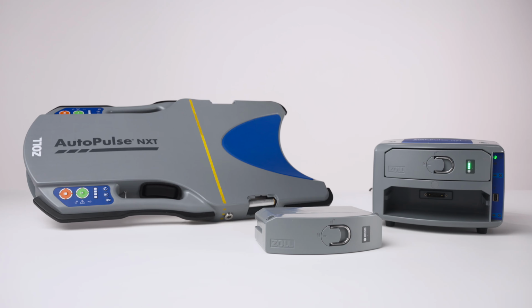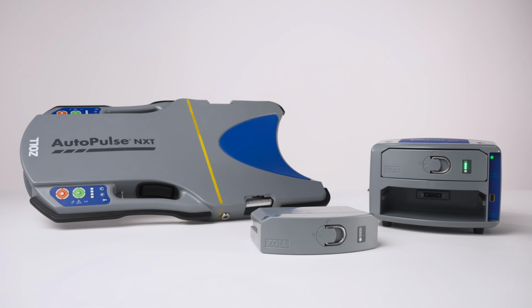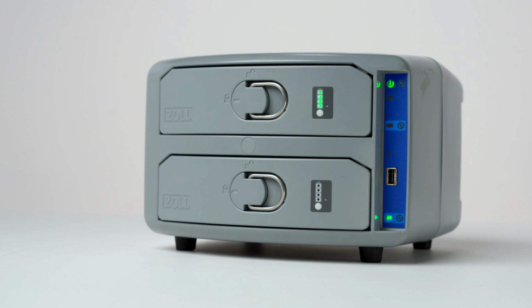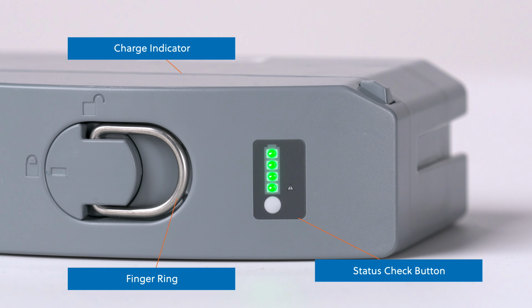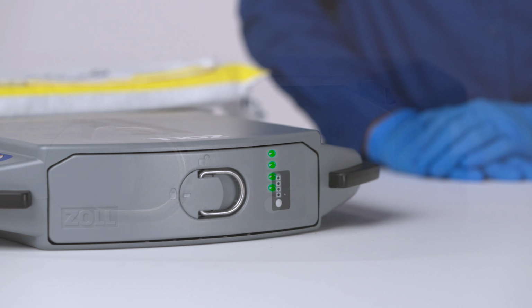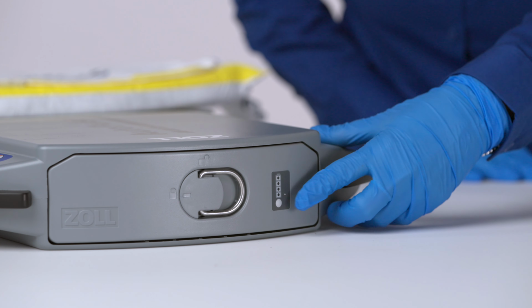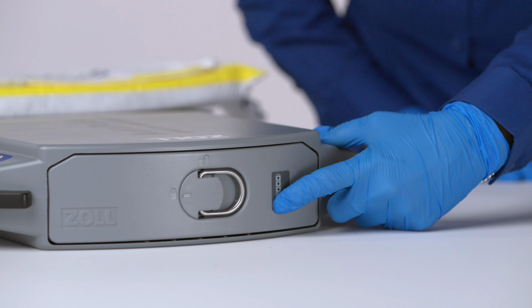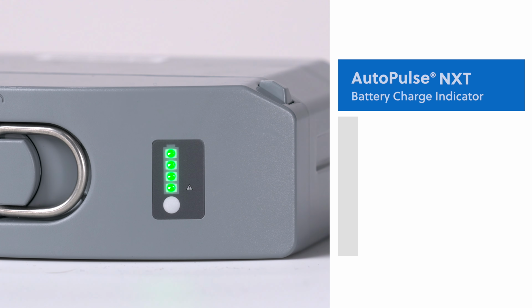When using the AutoPulse NXT system, you can check the battery charge status on the battery itself or in the battery charger. You'll find the battery charge indicator on the face of the battery next to the finger ring. This remains visible while the battery is in the platform. The number of lights illuminated indicates the charge level. 4 green bars mean the battery has over 75% charge. 1 to 3 green bars mean the battery has a partial charge. 1 bar means the battery's charge is very low and the battery needs to be changed.